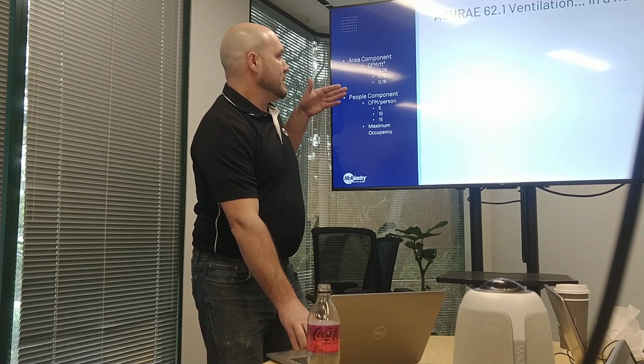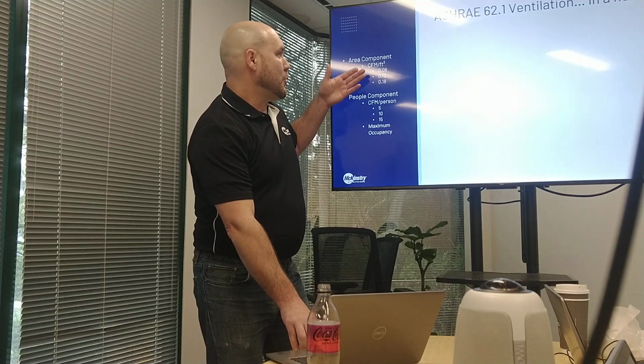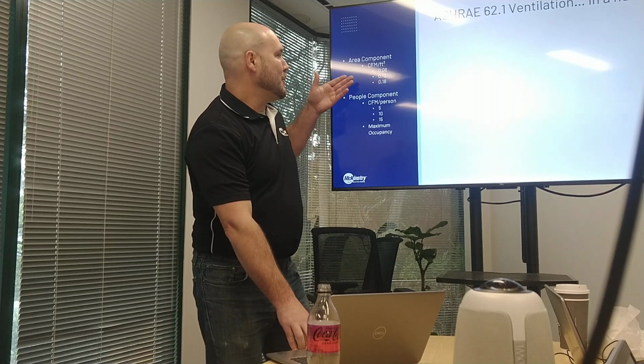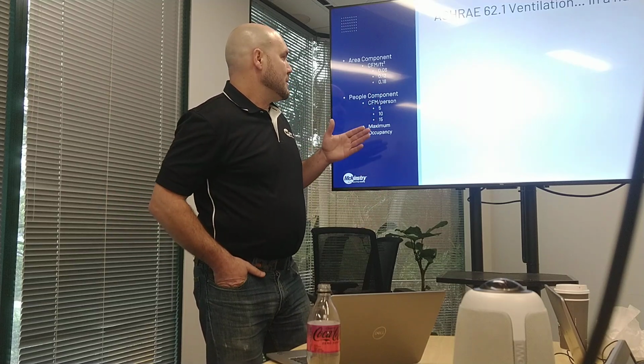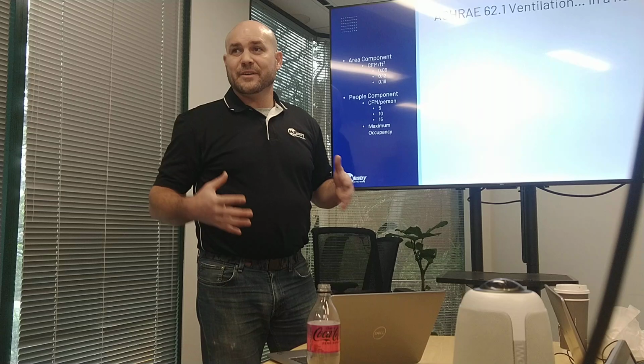So getting into ASHRAE 62 ventilation, there's kind of two components here: the area component and the people component. The area component is measured in CFM per square foot, and the three values that are usually given in Guideline 62 are 0.06, 0.12, and 0.18. Yes, they're just multiples of 0.06. Depending on the space type, like a fitness workout area, it's probably going to have a higher CFM per square foot. And there's also the people component, which is CFM per person, and that's usually 5, 10, or 15 CFM per person. And that is, again, based on the kind of activity that people are doing.